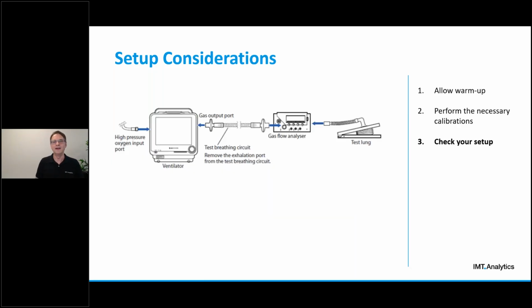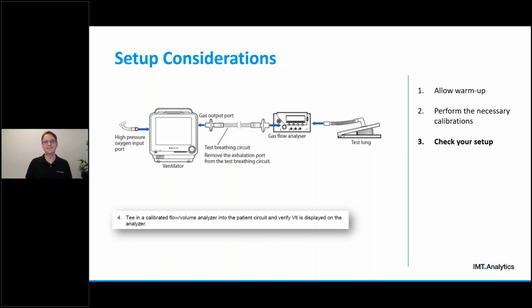Here's a second example. Again, the picture here is based on a very specific model of analyzer, but the picture doesn't clearly show which ports are supposed to be used of this gas flow analyzer here. So if you use a different one, you'll need to figure it out yourself again. And depending on the analyzer you use, this can look very different, eventually involving teeing in pressure, as we've seen in the previous example, or, for example, an oxygen measurement module. Here's the third example. This is a great one. In this case, there is only a very basic description of the setup, and everything else you need to figure out yourself.